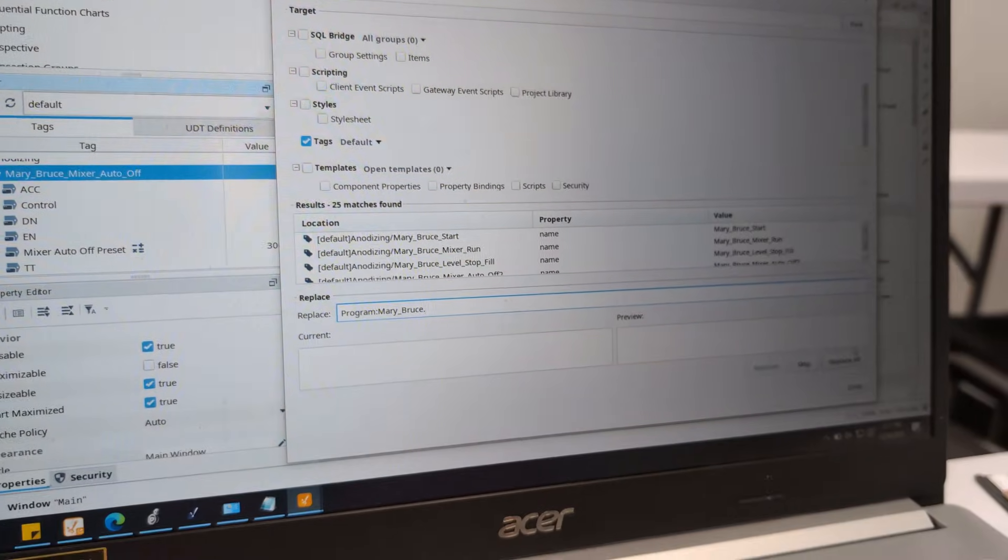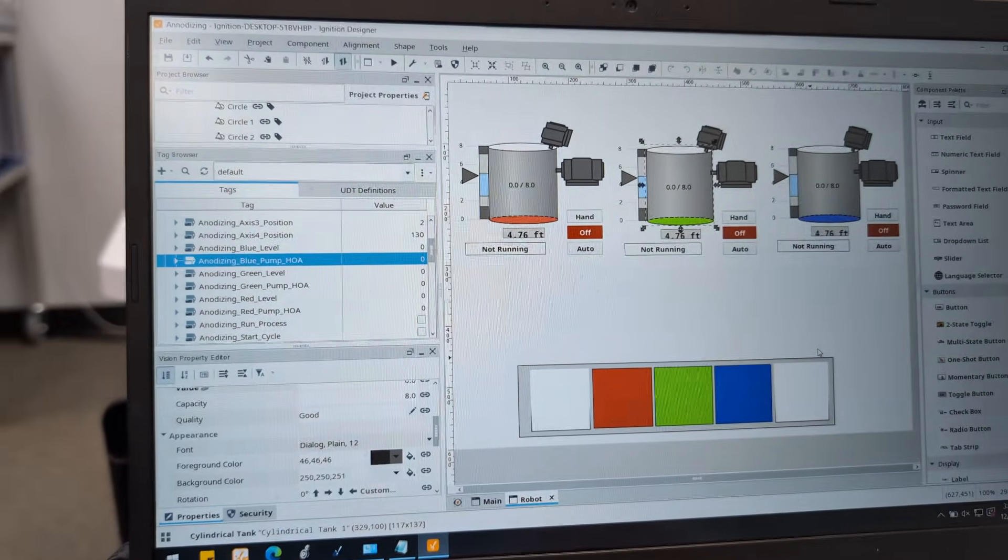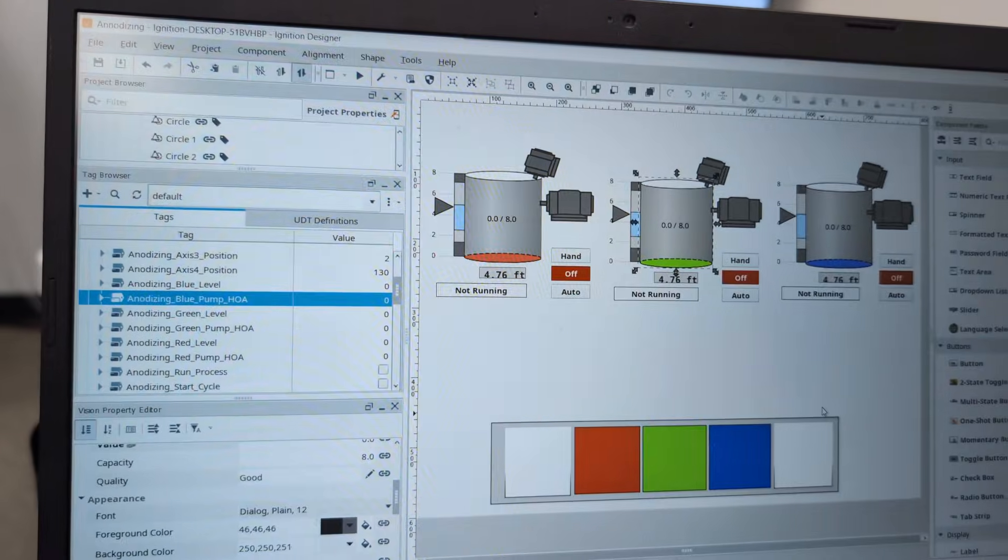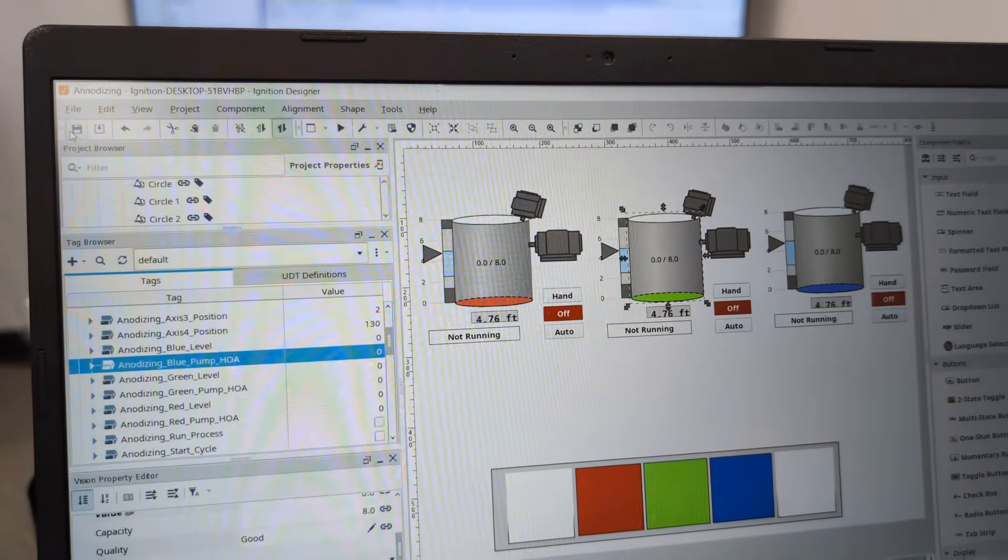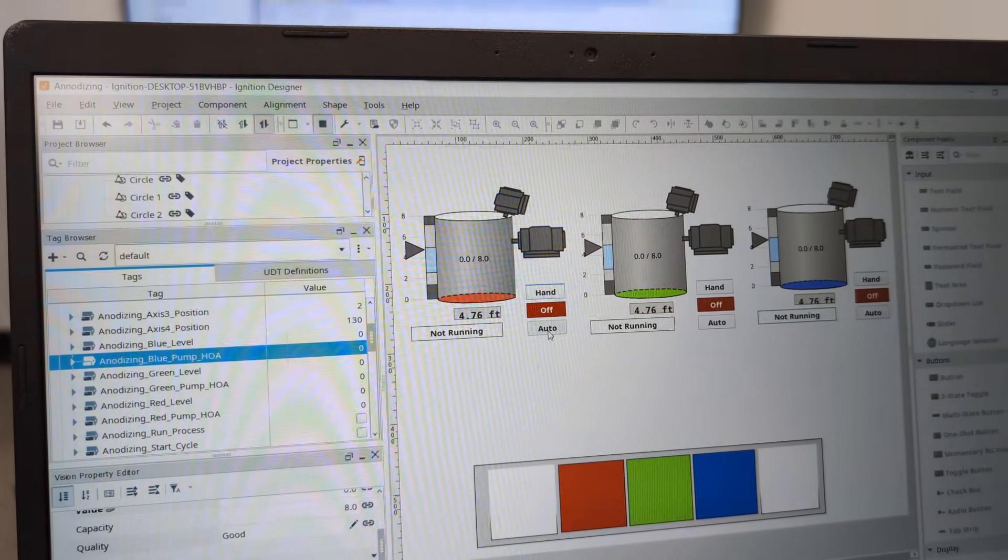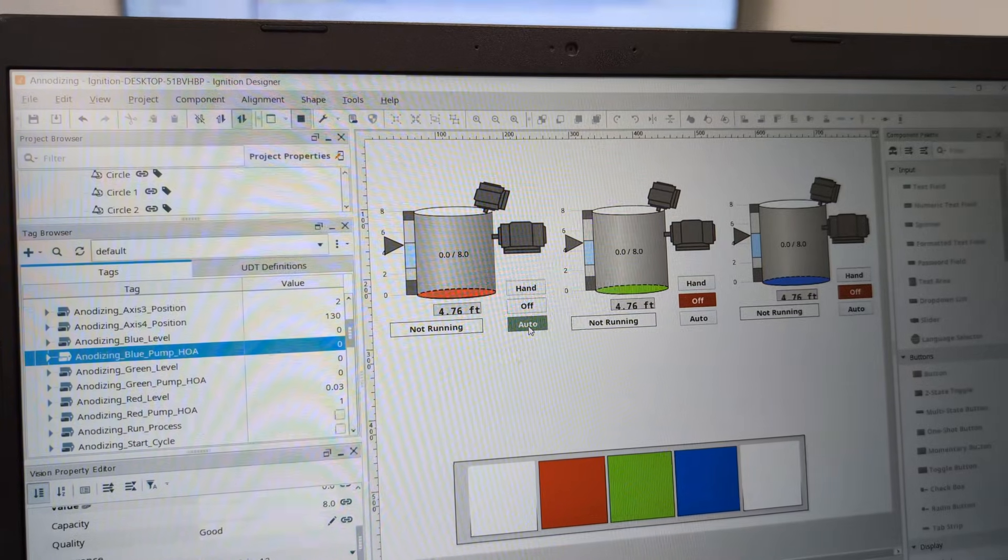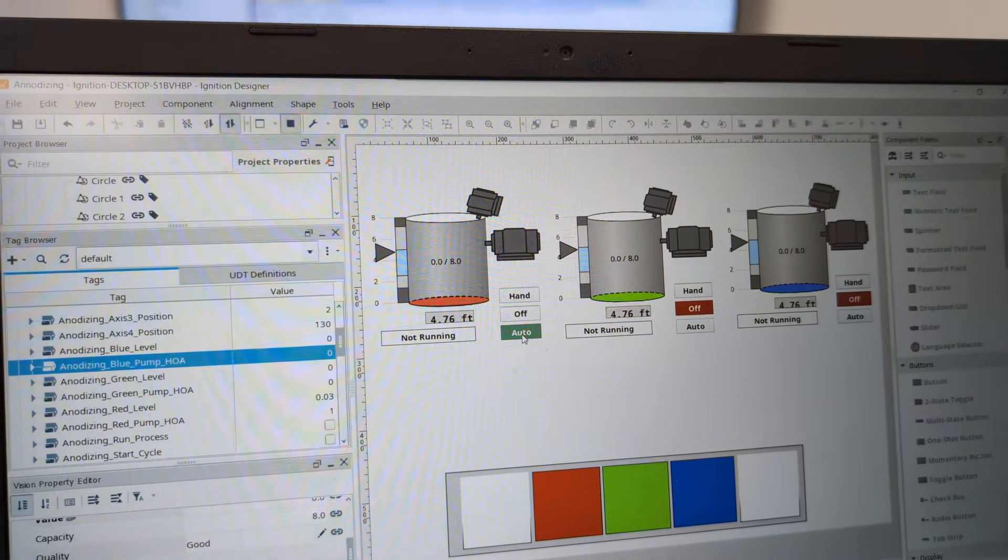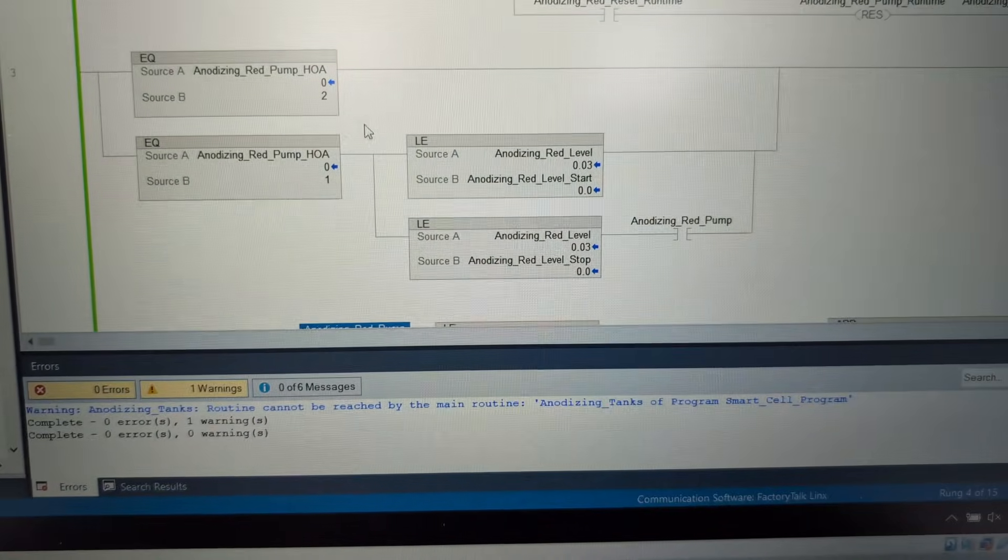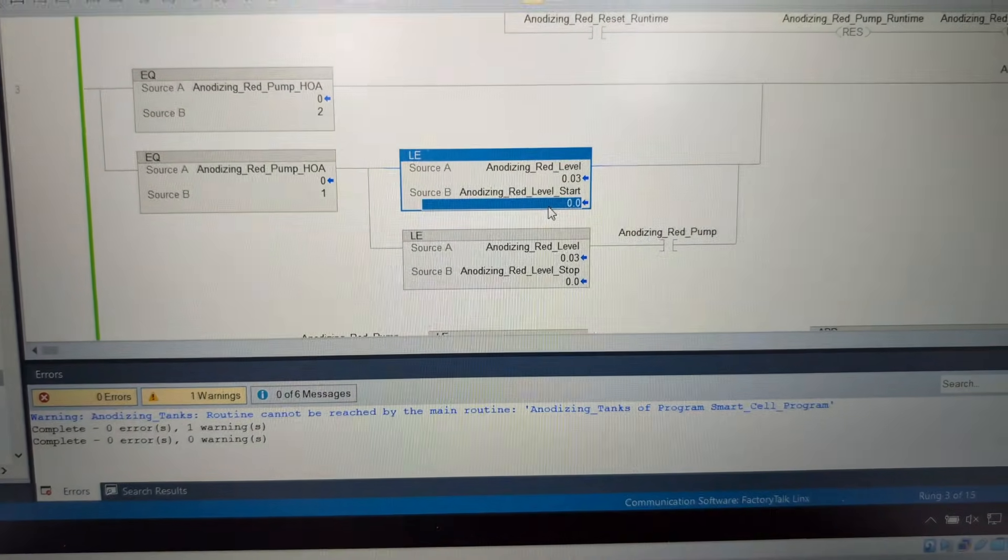So here those three tanks represent those three tanks and right now they're empty. We got our pump HOA, so you switch the red pump's HOA to the auto position - we want to go to auto, let's just see if it works. It's not working is it? Well how about that. Well that's why we do everything live on video so you see me screw up. Of course it's doing exactly what I told it because I created the tags and I didn't put any values in them.